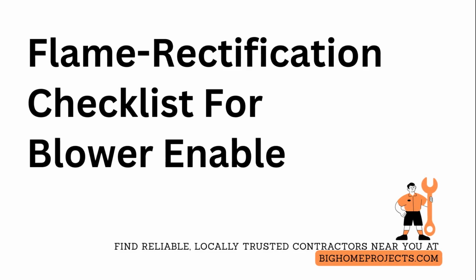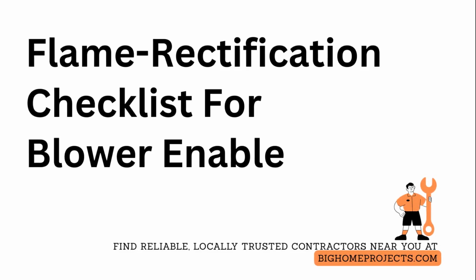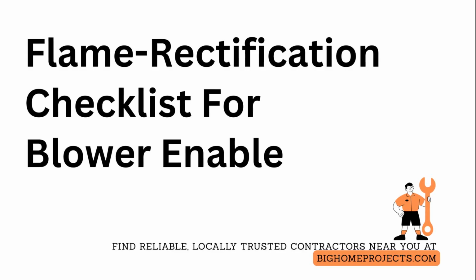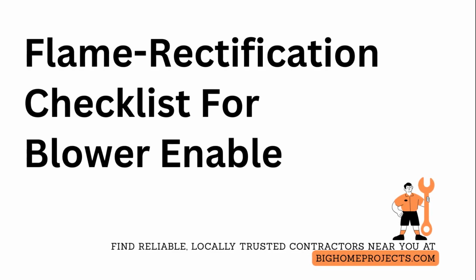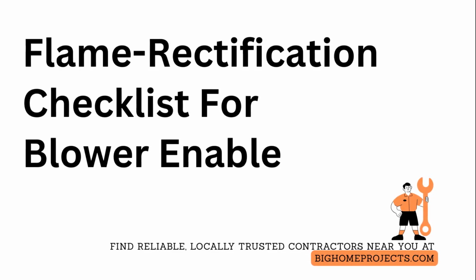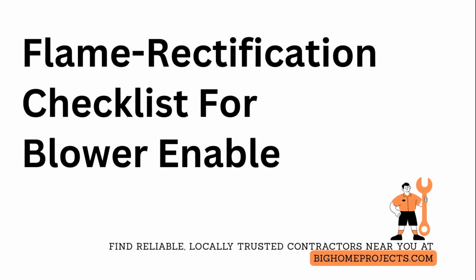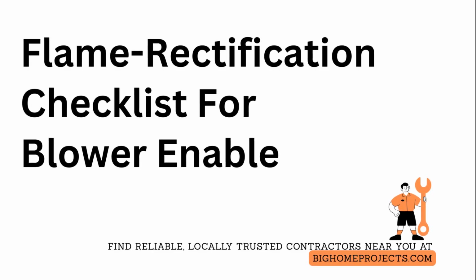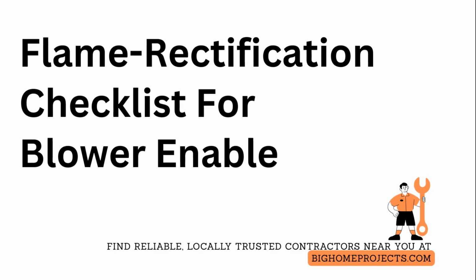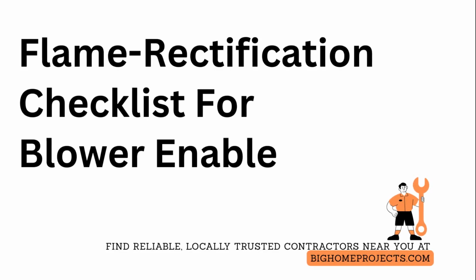Control boards must verify a strict safety sequence: limit switches, flame sensors, pressure and rollout switches, and proper inducer and ignition confirmation before the heating blower is allowed to start, to prevent dangerous furnace operation.